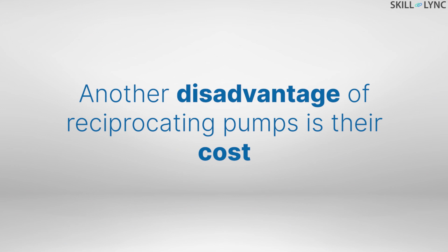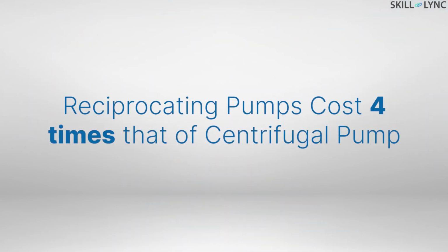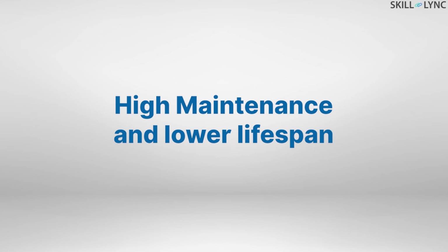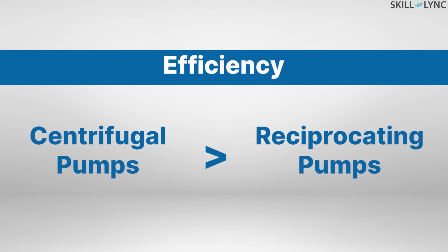Another disadvantage of reciprocating pumps is their cost. The reciprocating pumps cost as much as 4 times the cost of a centrifugal pump of similar specifications. This is because of the complex design of the reciprocating pumps. These pumps also have many more moving parts. This drives up their maintenance cost and reduces lifespan. The efficiency of reciprocating pumps is also lesser than centrifugal pumps due to the fact that they need to operate a wide variety of inlet and outlet valves.